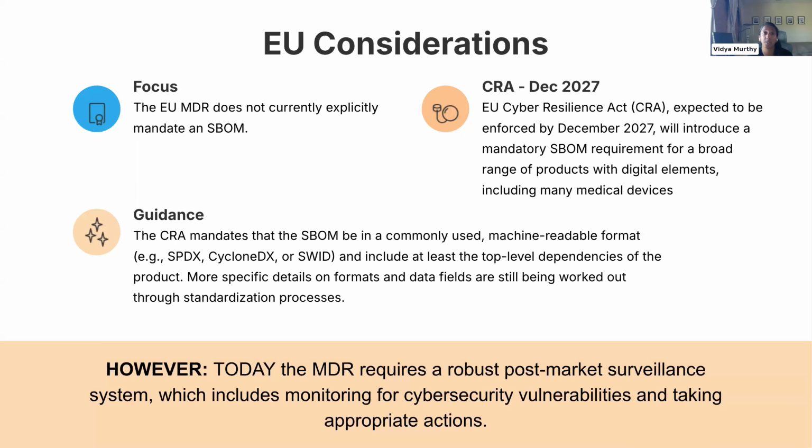There are some unique considerations for the EU. Currently, EU MDR does not explicitly state that they want an SBOM. We see the expectation that by 2027, there will be something in the EU Cyber Resilience Act to introduce mandatory SBOM requirements. What we have historically seen is that the EU in general tends to follow the same standards in terms of components included in an SBOM. So where the NTIA has defined what an SBOM is, it is expected that the EU will also have those same components as part of their minimum requirements.